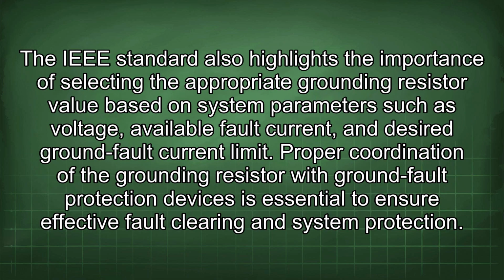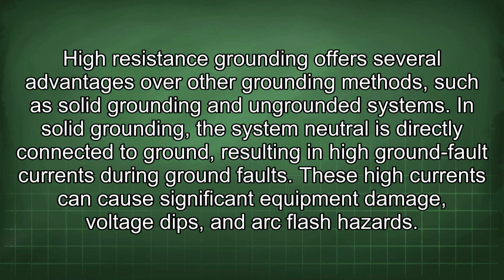The IEEE standard also highlights the importance of selecting the appropriate grounding resistor value based on system parameters such as voltage, available fault current, and desired ground fault current limit. Proper coordination of the grounding resistor with ground fault protection devices is essential to ensure effective fault clearing and system protection. High-resistance grounding offers several advantages over other grounding methods, such as solid grounding and ungrounded systems.